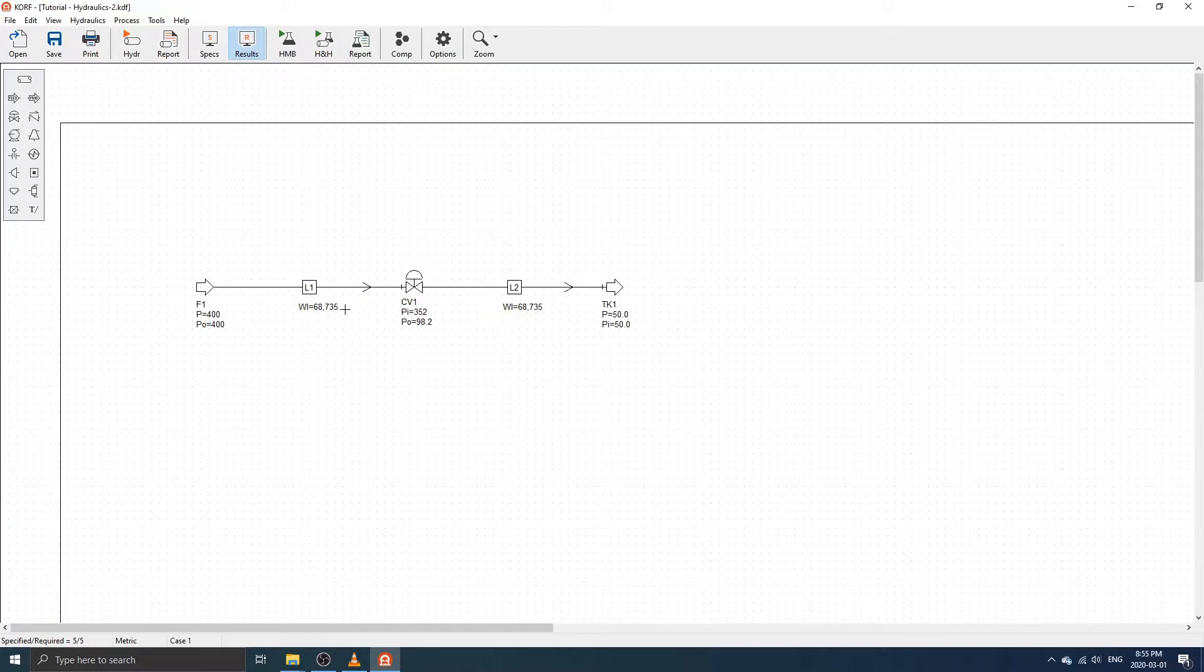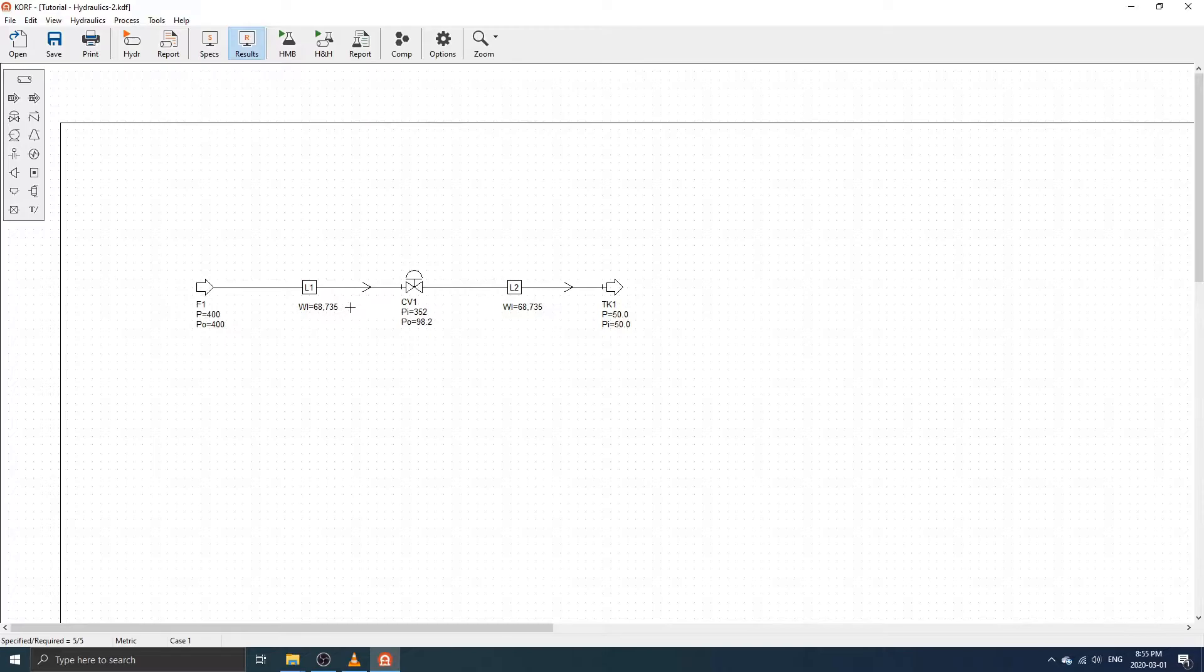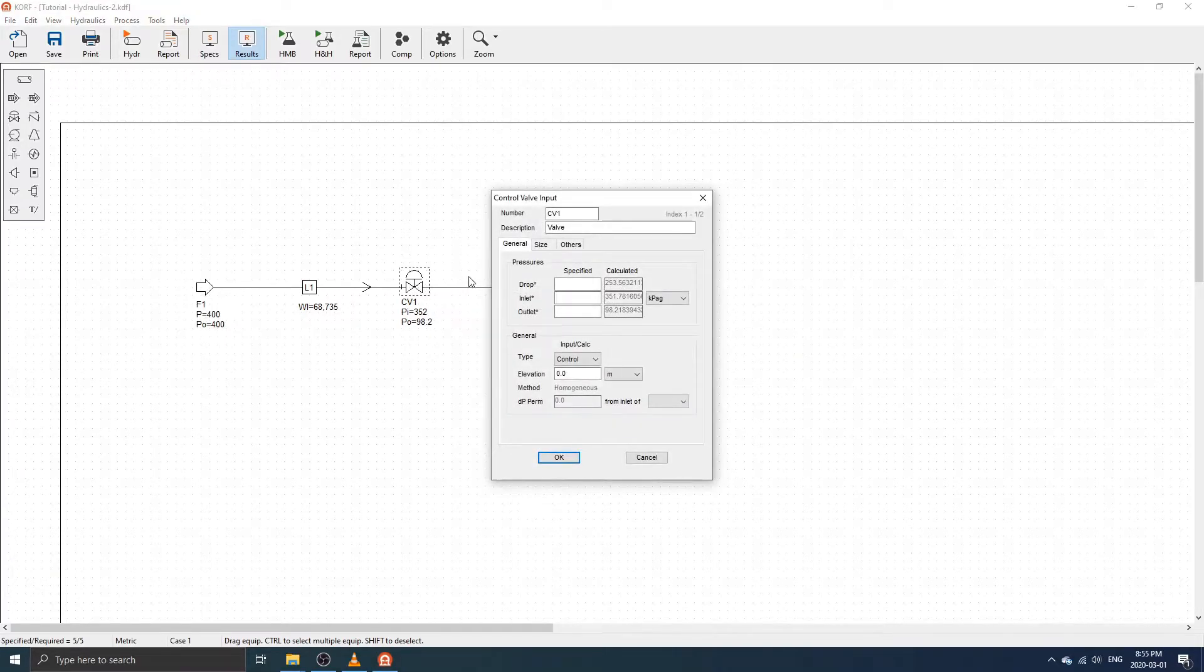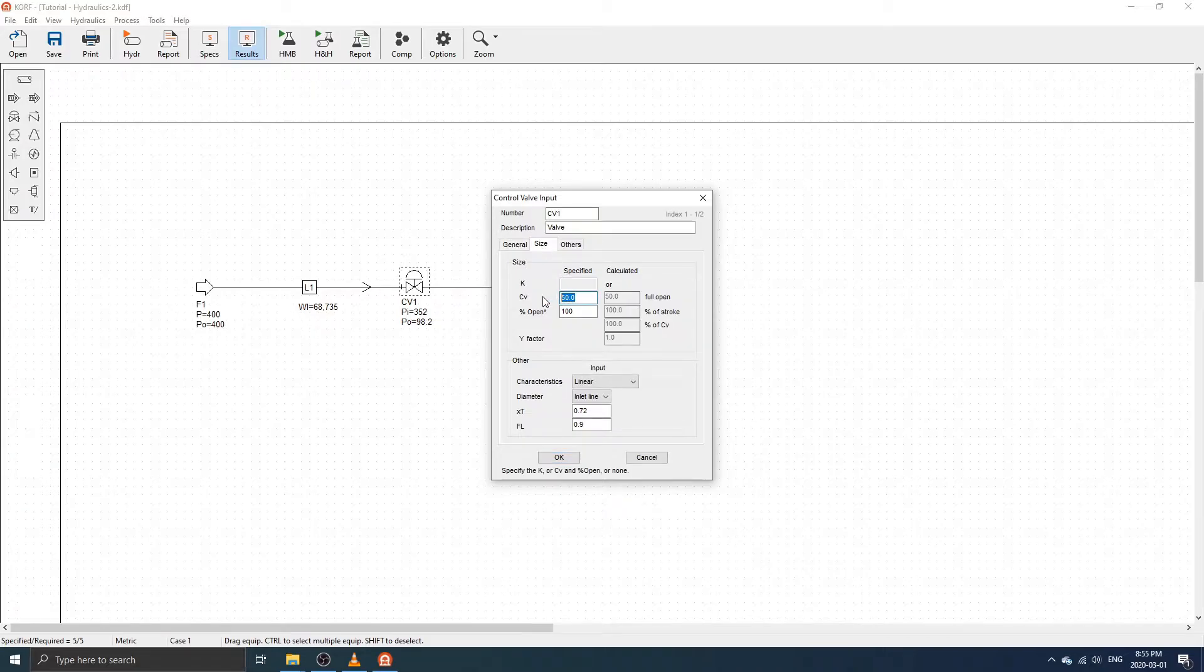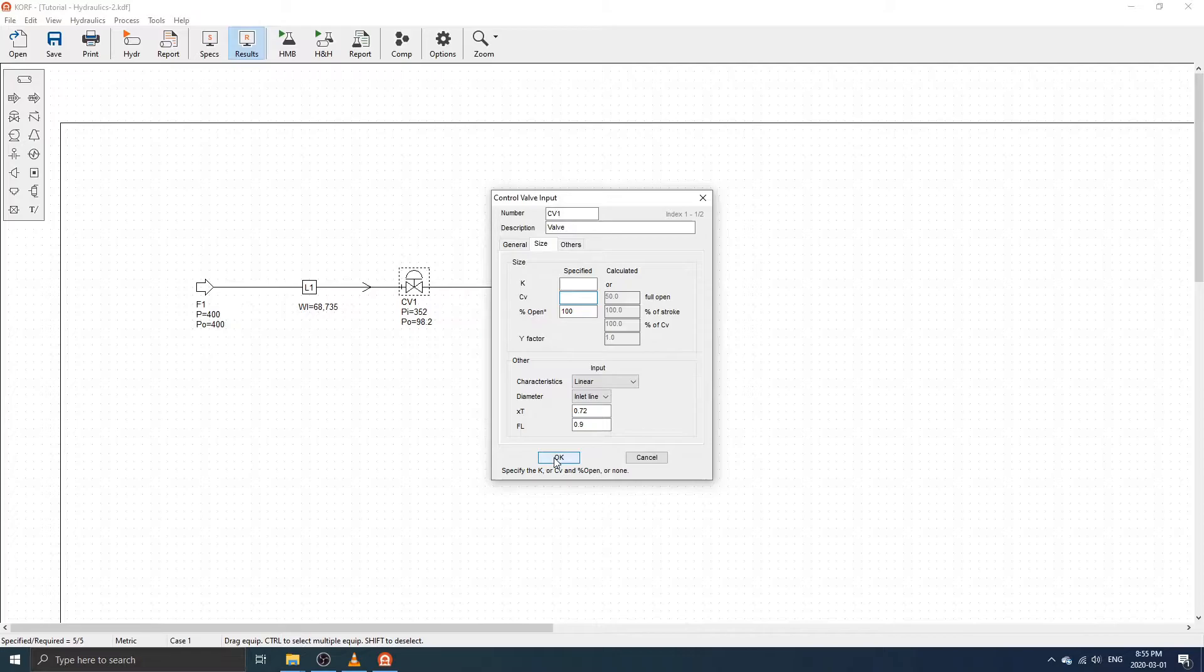Alternatively, you can calculate the control valve pressure drop, and thus valve size, by specifying the flow rate instead of the valve CV. To do this, double-click on the control valve, then select the size tab and delete the valve CV. Click OK to confirm the changes.